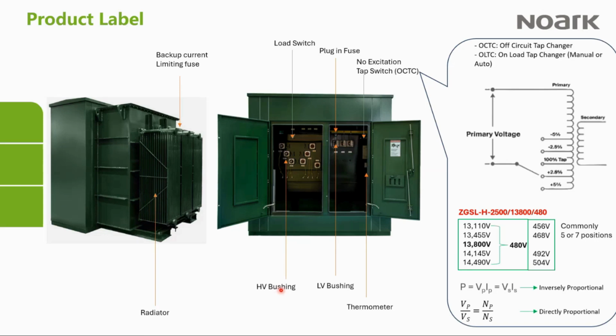So the bushing, firstly, what are the bushings for? Why do we need them? Basically, bushings are isolators that are used to bring power into the transformer, and their use is not limited to the transformer alone. You also use them on transmission lines, in substations, and so on. But when you're bringing power into this pad mount transformer, for example, the power has a rated voltage, so the potential is there. But remember that this pad mount transformer is grounded to the earth, so it's at zero potential. So you're trying to bring something with higher potential, maybe 12 kV or even 15 kV, into a device that is at zero potential. So you want to make sure that you don't have any kind of short circuiting around that.